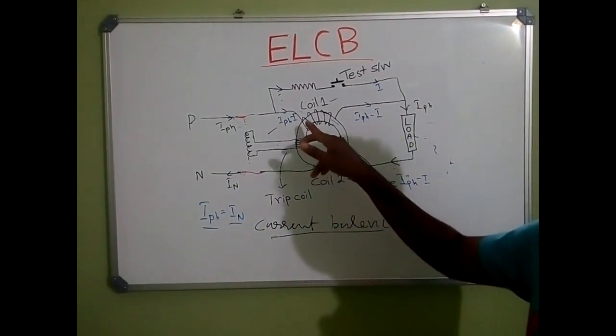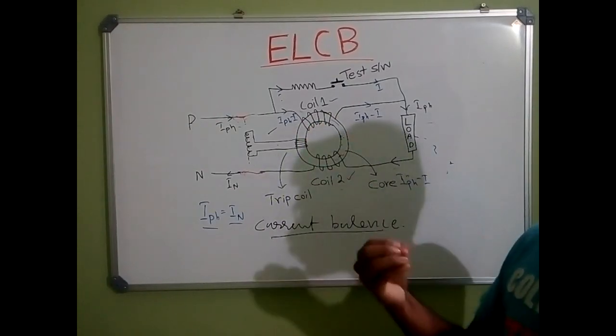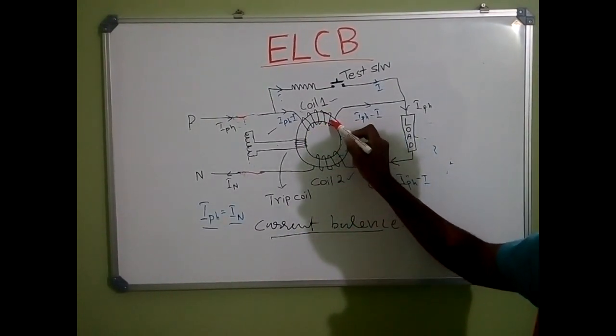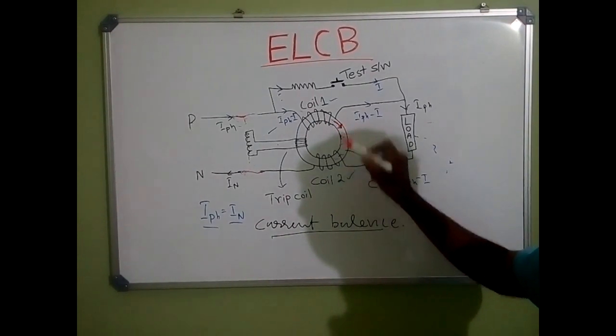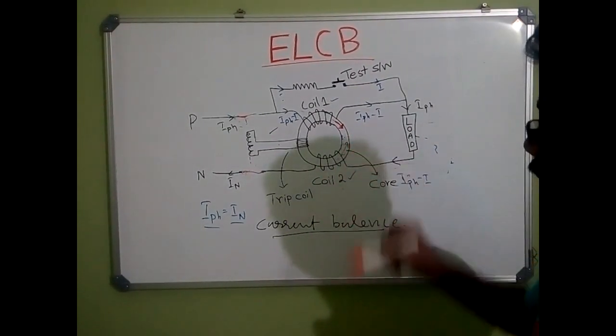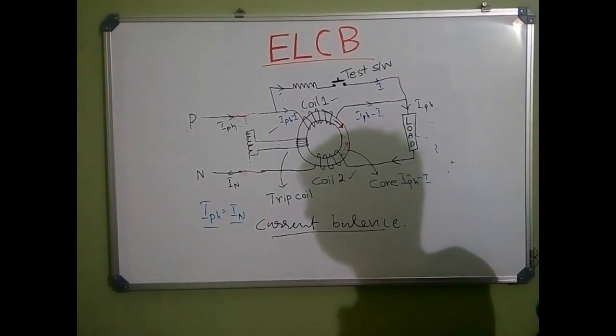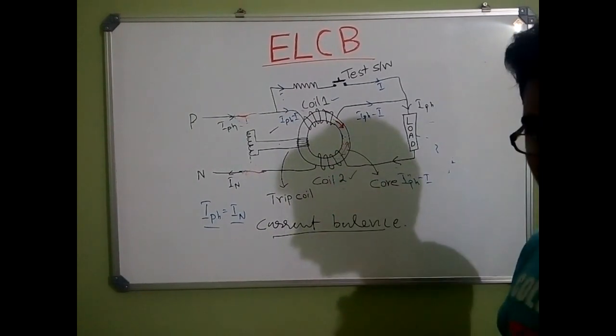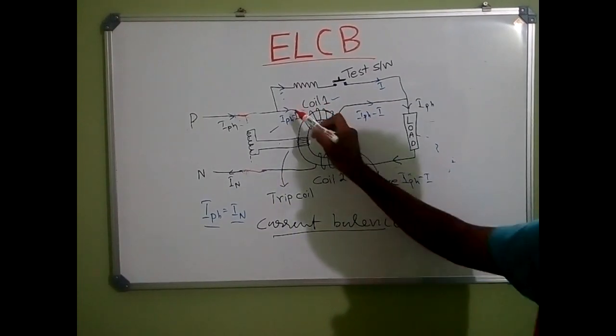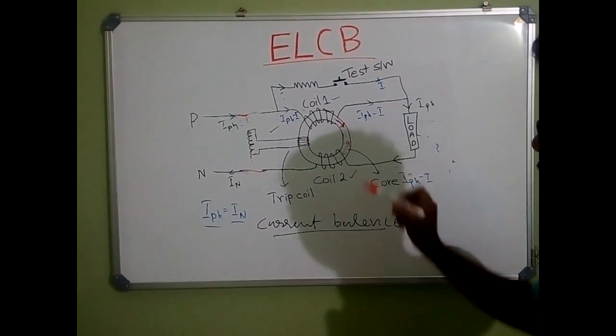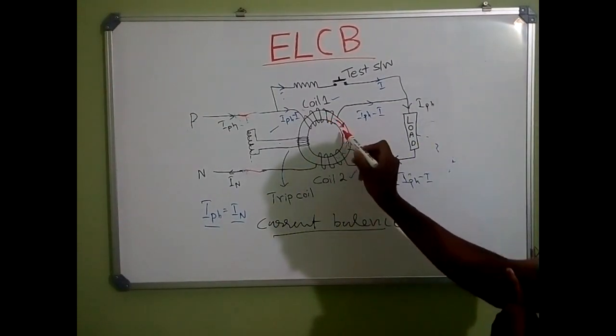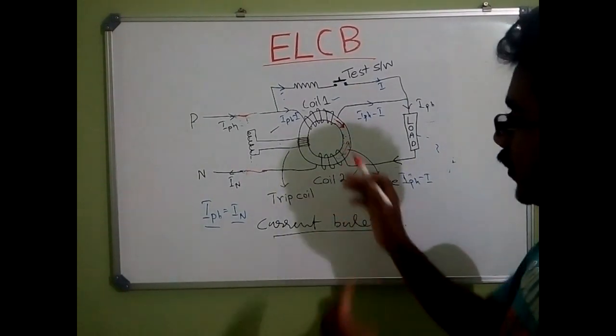When a current passes through a coil, an MMF is produced in that coil. Due to current through Coil 1, an MMF is produced in one direction. Due to current through Coil 2, an MMF is produced in the opposite direction. The number of turns in Coil 1 and Coil 2 are the same. So the MMF produced by Coil 1 and Coil 2 are equal. Since I-phase and I-N are equal, the net MMF in this core will be zero — one is clockwise and the other is anticlockwise.